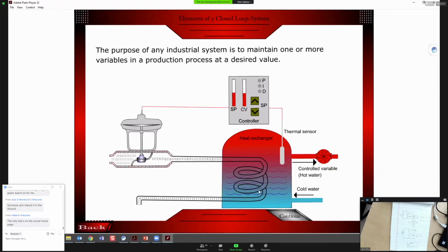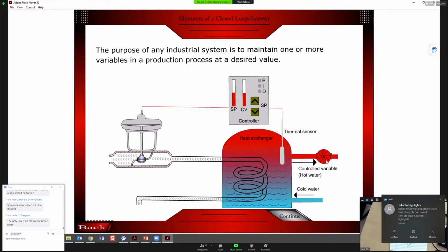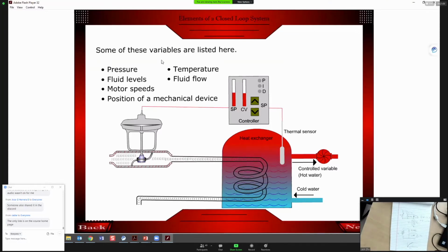This tries to maintain the temperature, because the cold water coming in from the city has a different temperature in the summer and the winter. But for the hot water used for the building or for industry, we want to set the temperature. We don't want that temperature to change. So that's why we need this automatic control system. It doesn't matter if your water comes in at 5 degrees or 15 degrees. The output water will always be at whatever you require, maybe 50 degrees or maybe 80 degrees. With closed loop control, we can control lots of different things. So this is the process. We can control pressures, water levels, motor speeds, temperatures, or even flows.